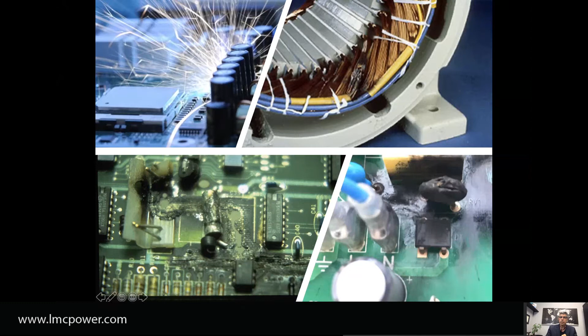Motors are being affected, circuit boards are being affected. Even the MOVs inside the unit designed to protect the circuit get burnt because they only have a very limited amplitude to protect. A lot of times manufacturers will size the MOVs big enough to comply with certain norms, but not necessarily to protect against external transients or transients higher than required.